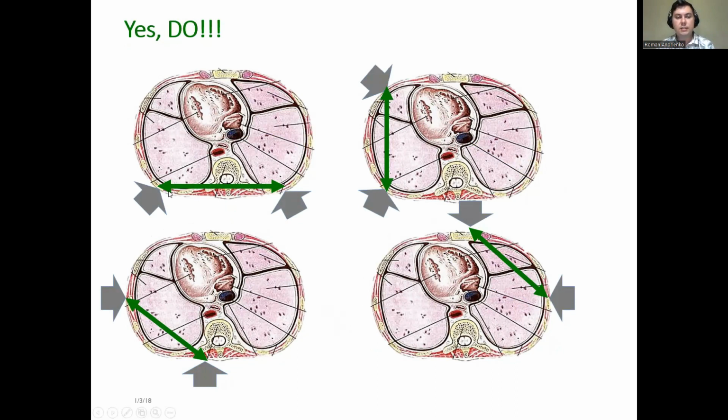It is simple. We use the rule of the quarters. So if we take the full circle, like we imagine that we're looking at the body from above, we see that circle. We are not putting our split electrodes too far from one another. The maximum distance between them is 1/4 of the entire circle here. So correct, correct, correct, also correct.